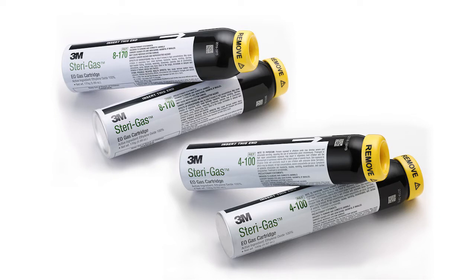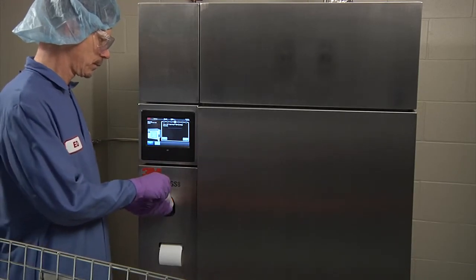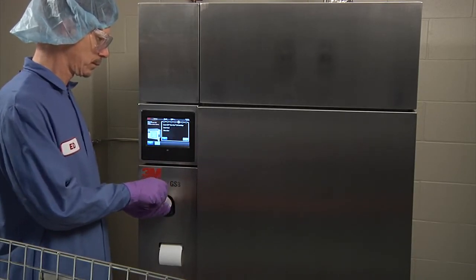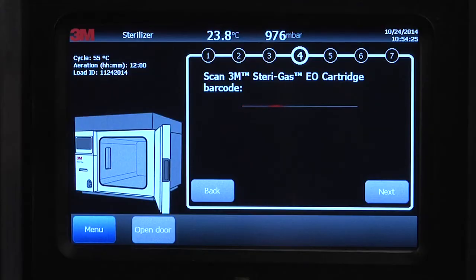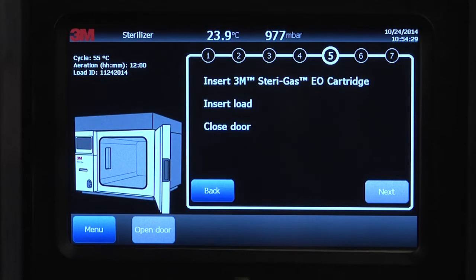Only use 3M Sterigas EO gas cartridges, as other ethylene oxide cartridges have not been validated for safety and performance in the GS series sterilizer. Place the cartridge barcode into the barcode scanner on the sterilizer. If the cartridge information is valid, the sterilizer will accept the barcode, record the lot number, and print the lot number as part of the cycle report.